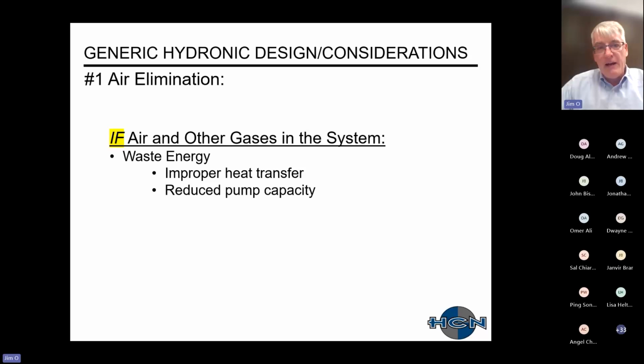So first, you have to be careful about air elimination. Your hydronic system is usually operating at higher pressure, but there are parts of it that could be operating at a lower pressure. So air and other gases will get into the system, or you should say when they get in there. What will happen is that air and gas is basically not water.